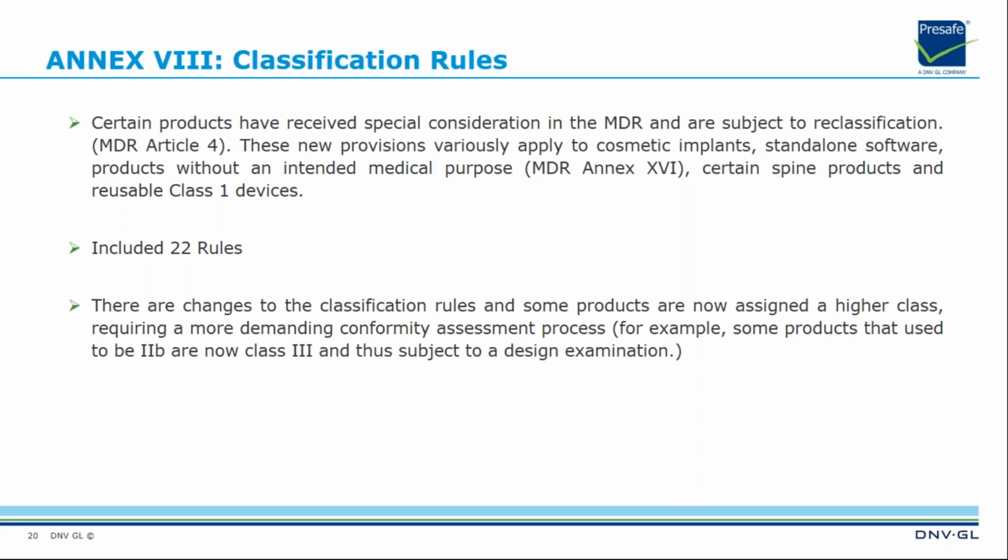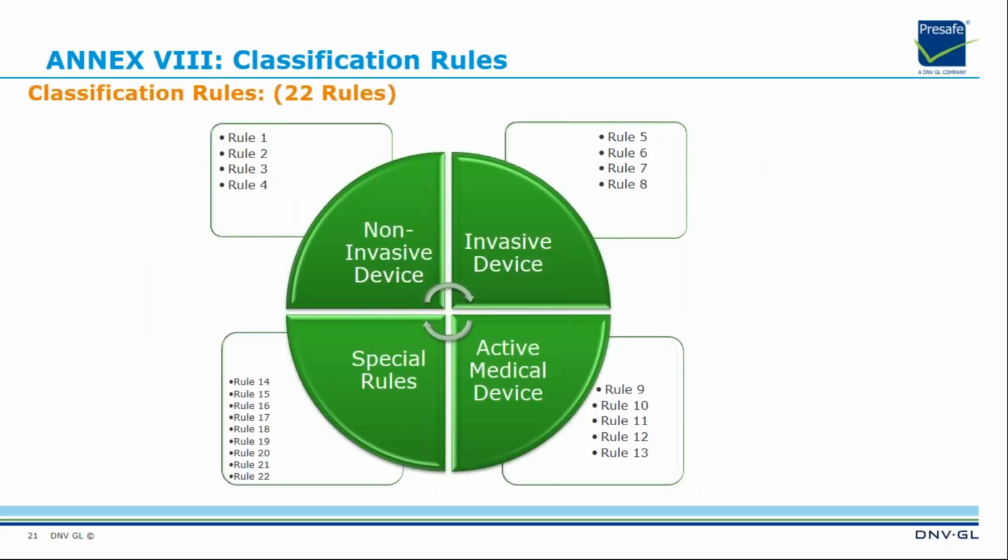So Rule 1 to Rule 4 is relevant to non-invasive devices. Rule 5 to Rule 8 is relevant to invasive devices. Rule 9 to Rule 13 is relevant to active medical devices. And from Rule 14 to Rule 22 are the special rules.